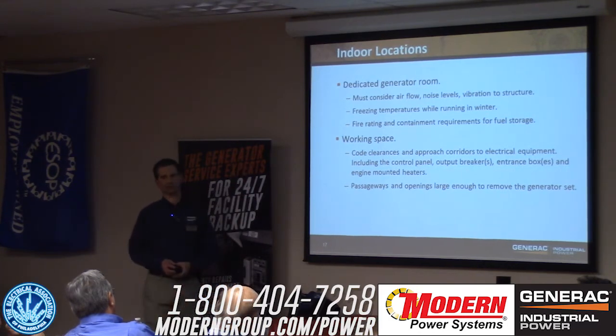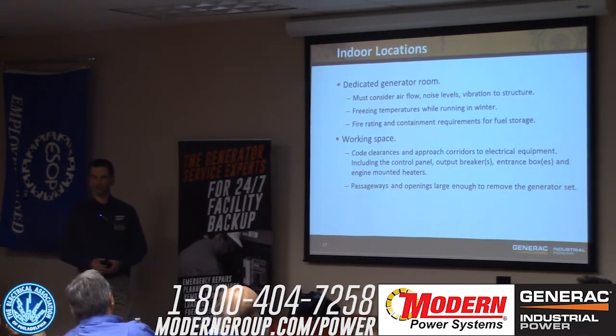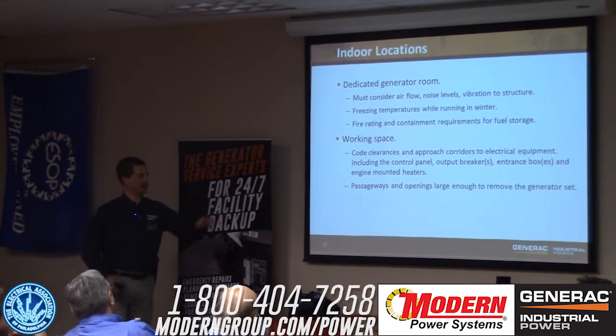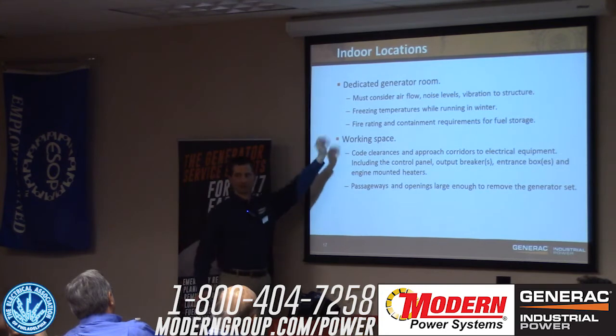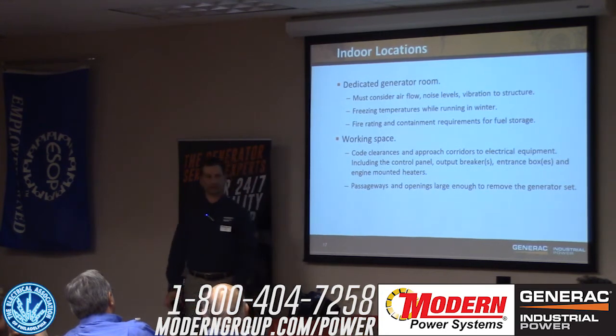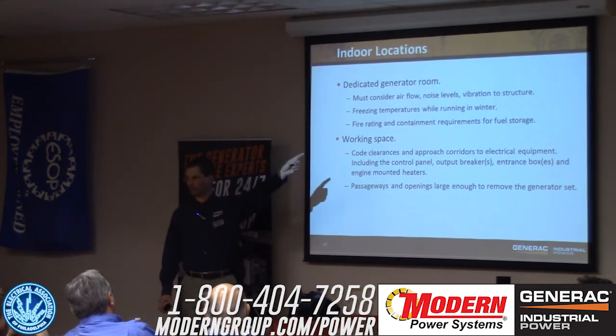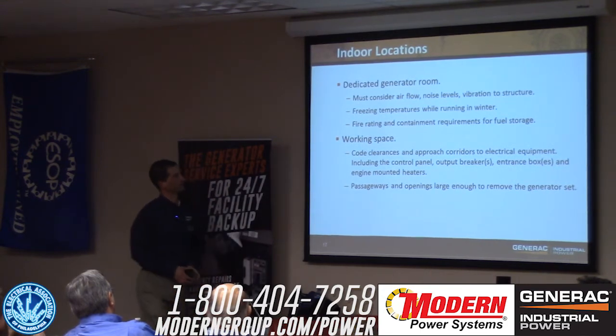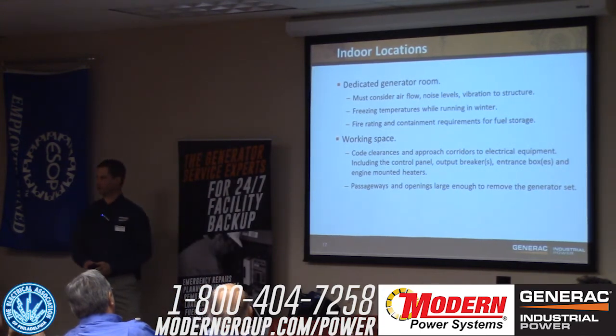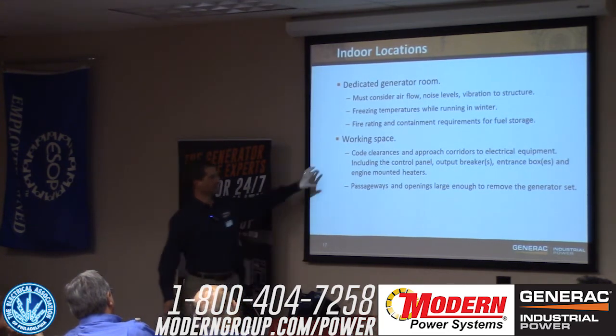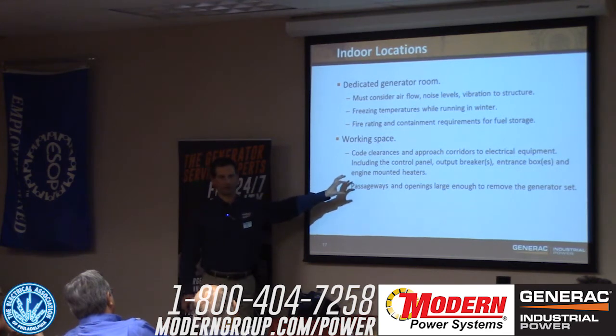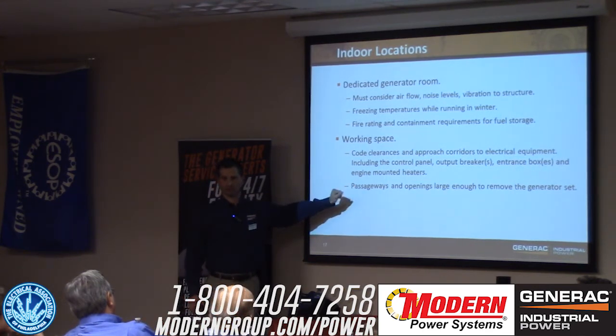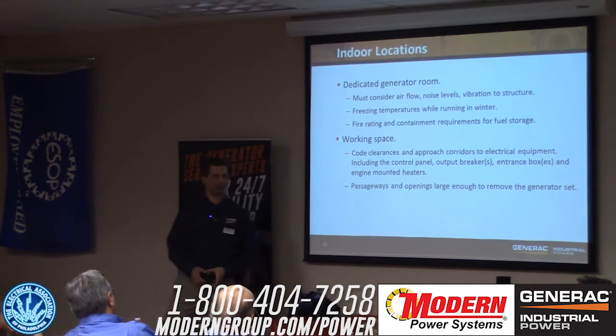You've got to have that airflow moving through the room to get the air out. When that machine starts, the room is going to get really chilly in the wintertime - I hope it's not wet pipe sprinkler systems overhead, or we're going to have a bunch of frozen pipes. The room has to be fire rated, there has to be fire suppression in there, and you've still got to maintain all the NEC required clearances around the machine. That has to be taken into account as well.